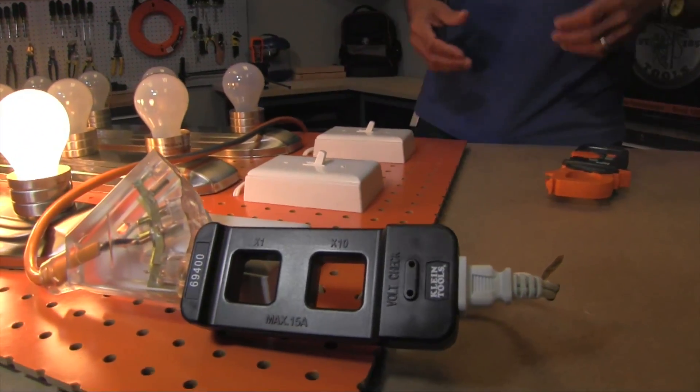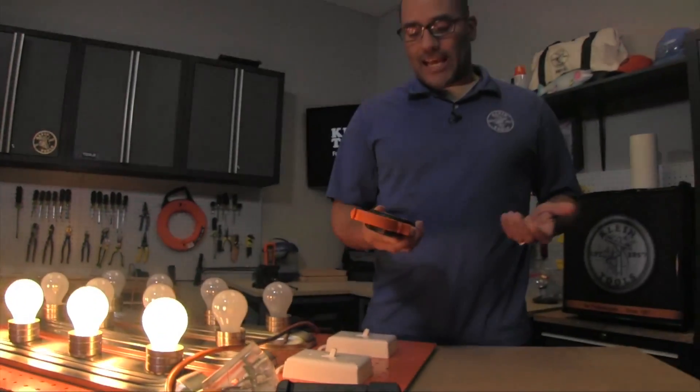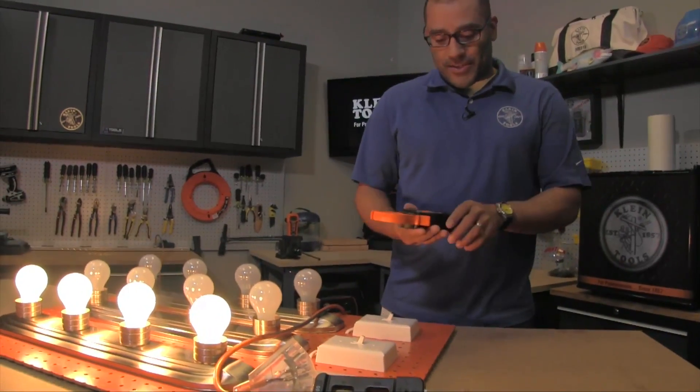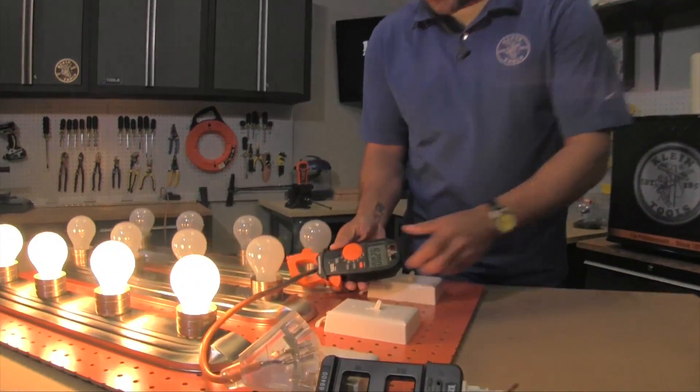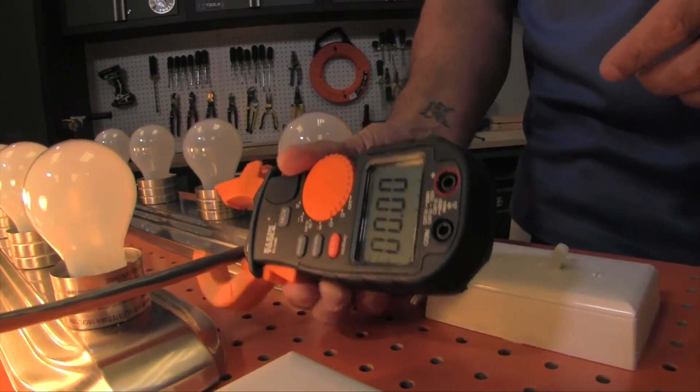If you wanted to check the amperage of this bank of lights that I have lit right here and you wanted to use a clamp meter, you would think just clamp on to this and you get your amperage reading. What you'll see is that you actually don't get a reading at all.